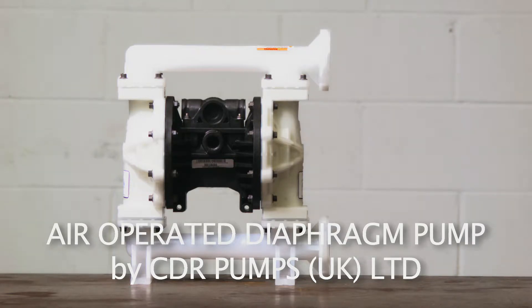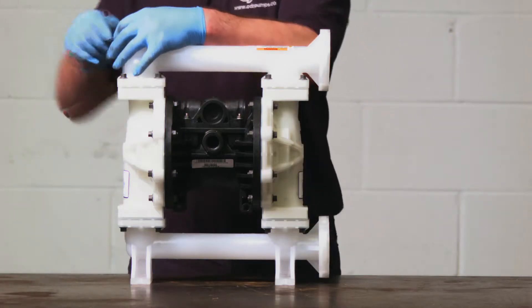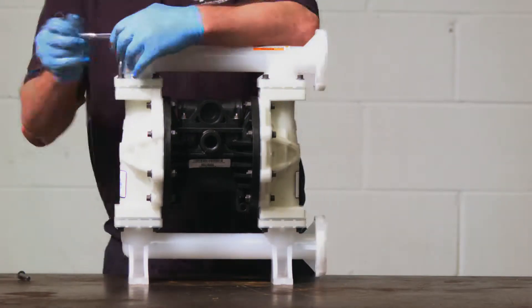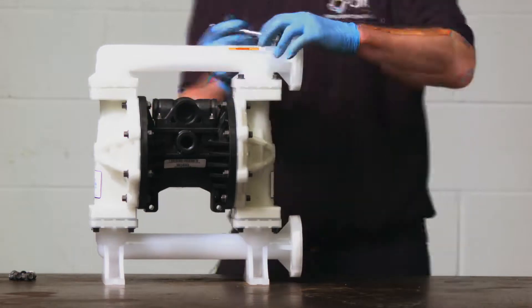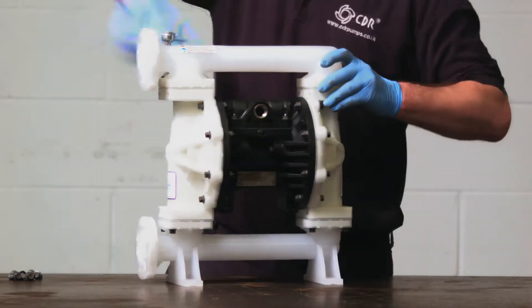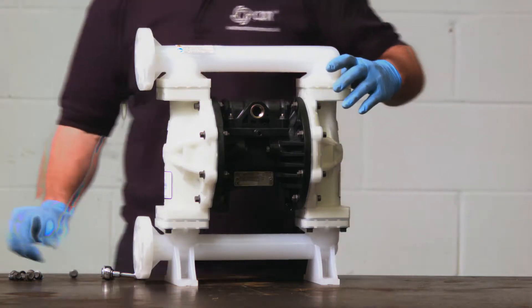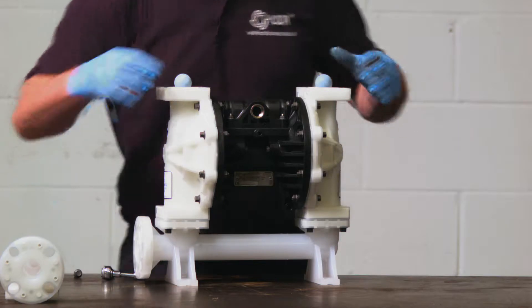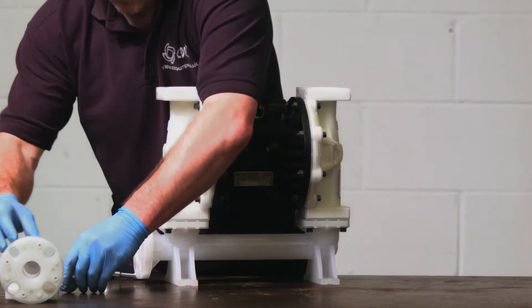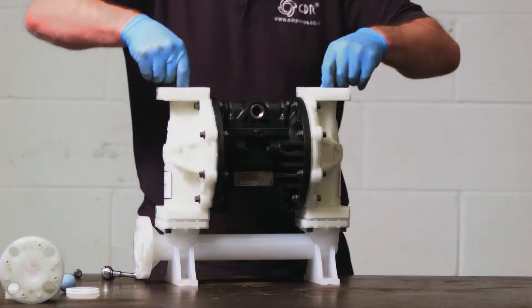When stripping down any pump, it is important to make sure that it is clean and free from all contaminants. To strip down the air-operated diaphragm pump, you firstly remove the discharge manifold by removing the fixing bolts at the top. On removing the manifold, you should see two balls set on top of the ball seats. Remove the balls, remove the seats, and then remove the O-rings that are sat in the recess.